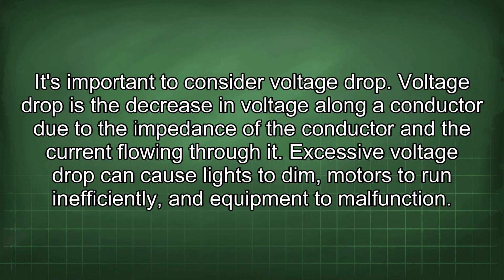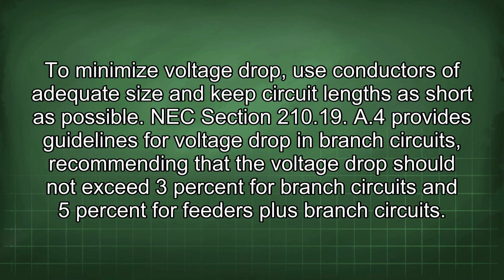It's important to consider voltage drop. Voltage drop is the decrease in voltage along a conductor due to the impedance of the conductor and the current flowing through it. Excessive voltage drop can cause lights to dim, motors to run inefficiently, and equipment to malfunction. To minimize voltage drop, use conductors of adequate size and keep circuit lengths as short as possible. NEC Section 210.19(A)(4) provides guidelines for voltage drop in branch circuits, recommending that the voltage drop should not exceed 3% for branch circuits and 5% for feeders plus branch circuits.